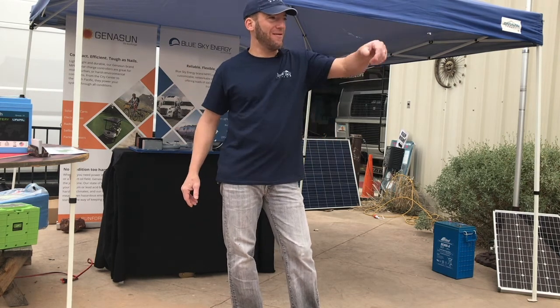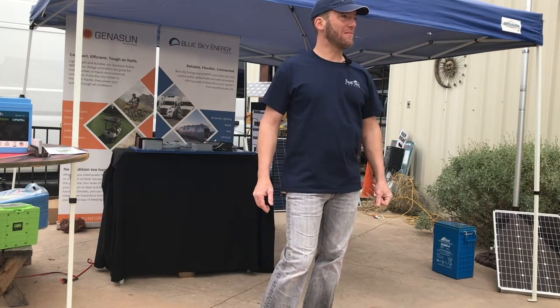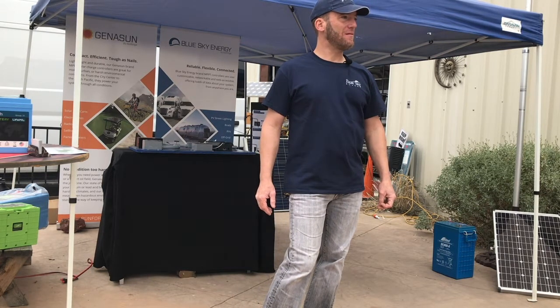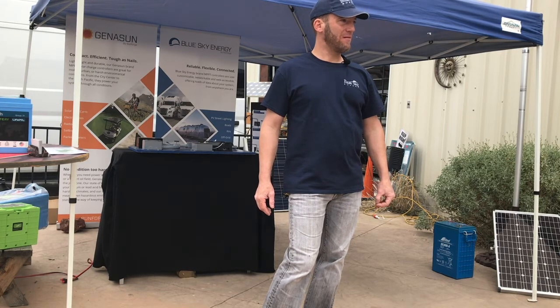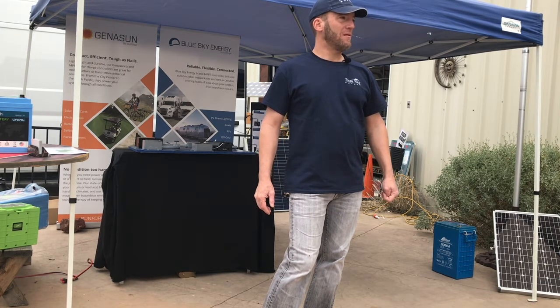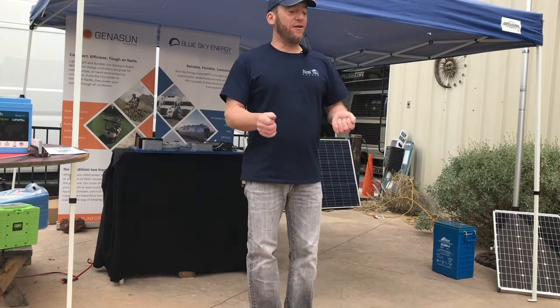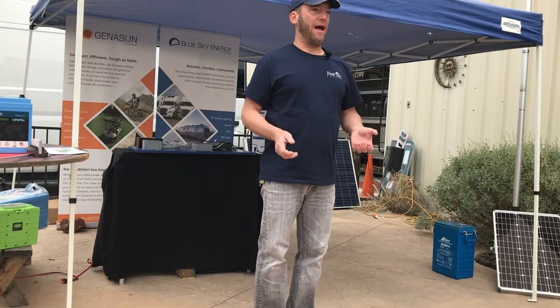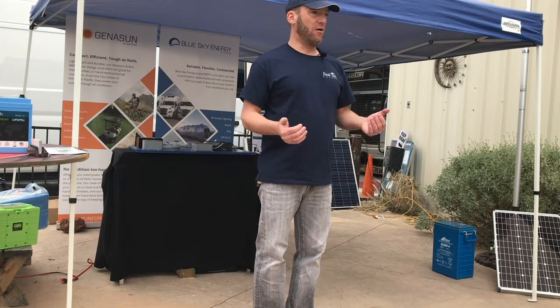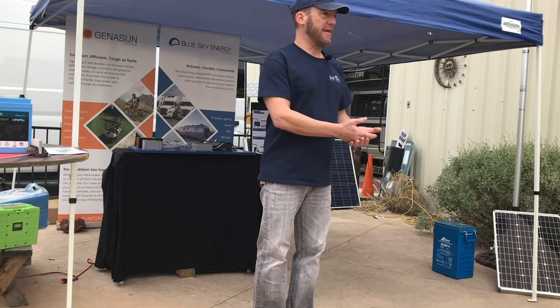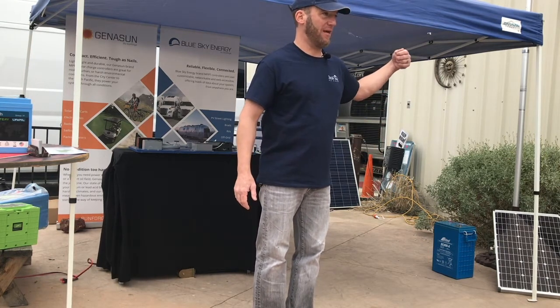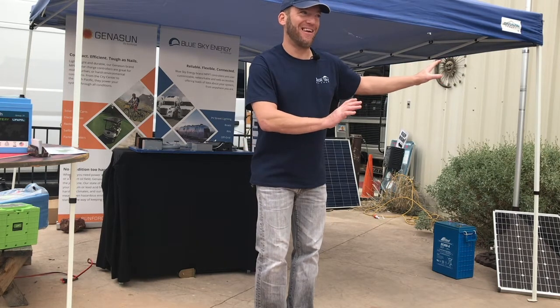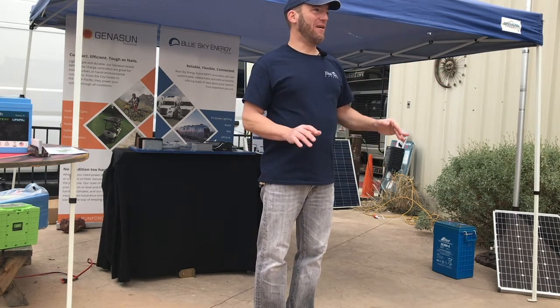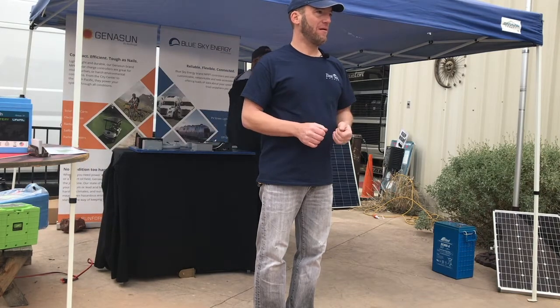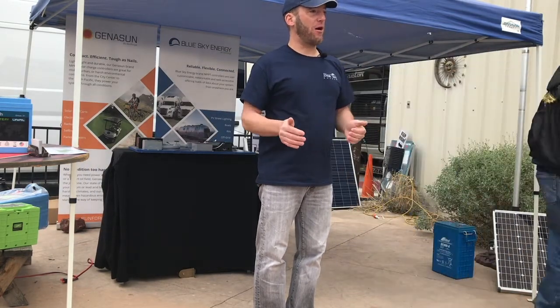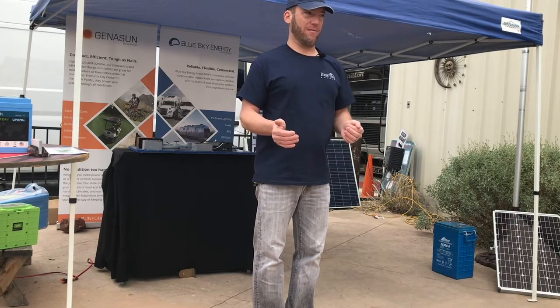Before we get too far along, for those of us not as well informed—are you saying that if you disconnect your batteries to change them, you do irreparable damage to the controller? No, what I'm saying is whenever you disconnect a battery, ideally you don't want to have a charge source actively charging it. So we recommend, for example on our controllers, that you disconnect the PV input, or pull the fuse on the PV input, or do it at night if there's no fuse. But when you disconnect that controller from the batteries, I've never had that cause irreparable damage to a controller—it's still just not advisable.